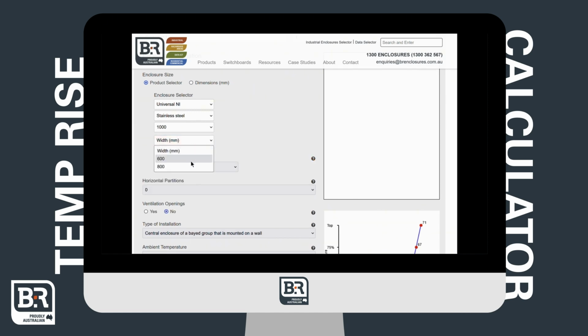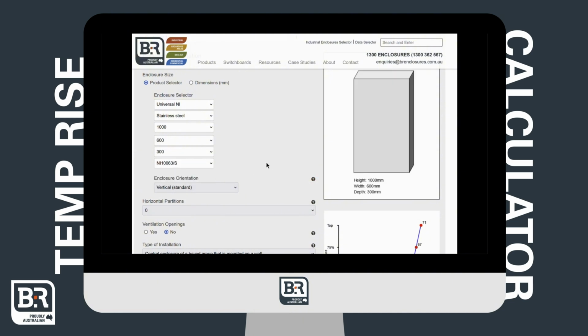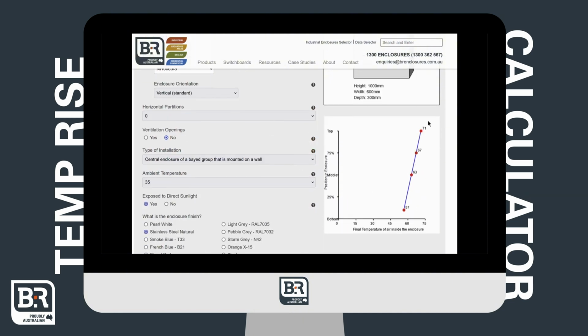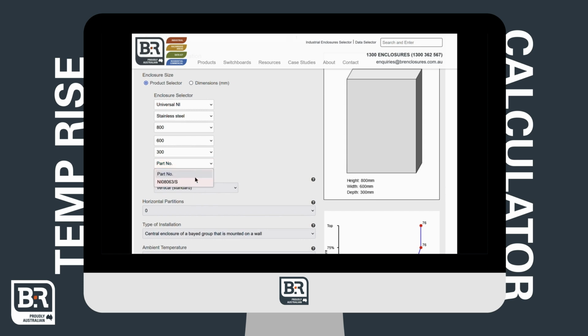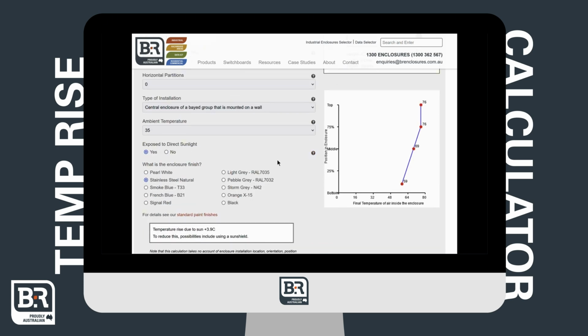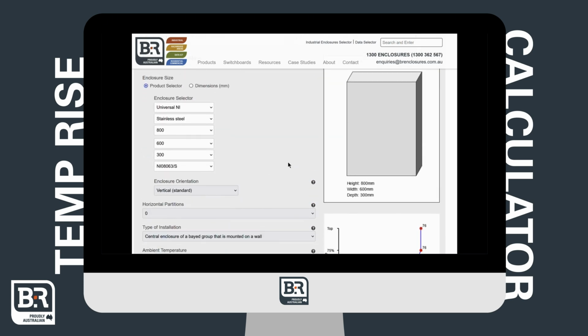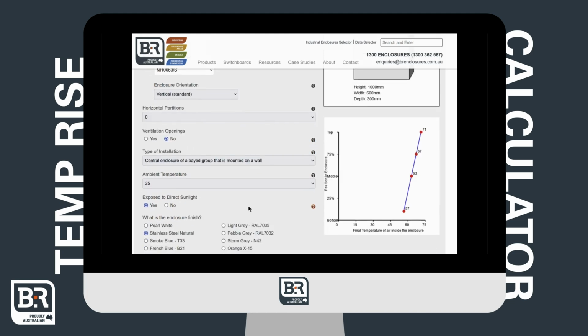Trying 800 by 600 by 300 mm causes the temperature to rise to 76 degrees. However, adding a sunshield can reduce it by around 4 degrees, just enough to bring it back into range. For extra safety, the larger enclosure is the recommended option.